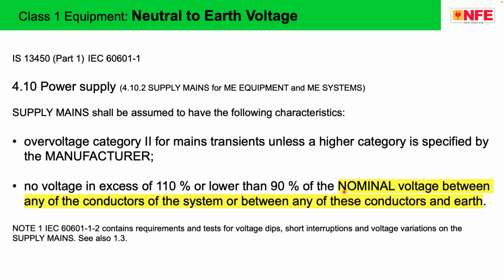These demands by biomedical equipment manufacturers are made because, first of all, probably they don't know the subject. Most often they don't know why the equipment is failing. The equipment may be failing because there is one more parameter you see here at the top. Overvoltage category 2 for mains transients specified by the manufacturer is required. It is the responsibility of the owner of the hospital to ensure that the installation category is maintained. So it is not the voltage, it is the categorization, and maintaining the categorization will protect your equipment.